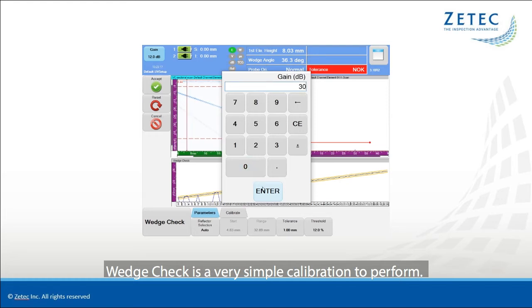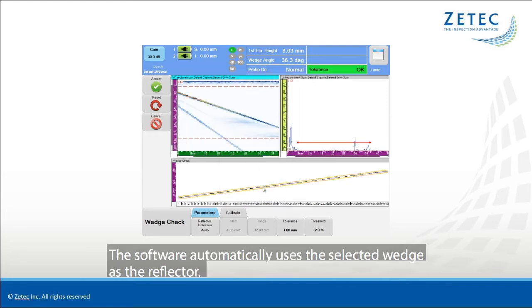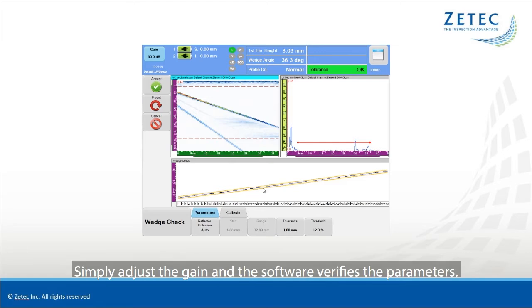Wedge Check is a very simple calibration to perform. The software automatically uses the selected wedge as the reflector. Simply adjust the gain and the software verifies the parameters.